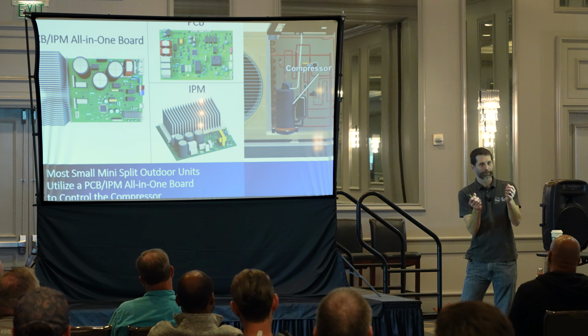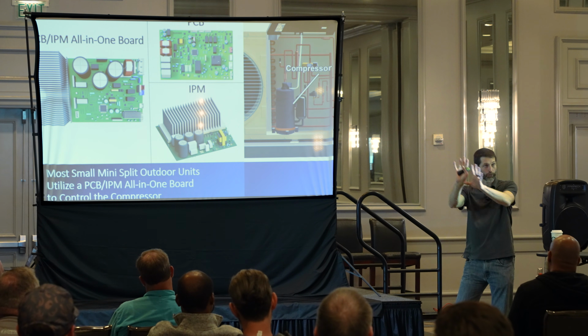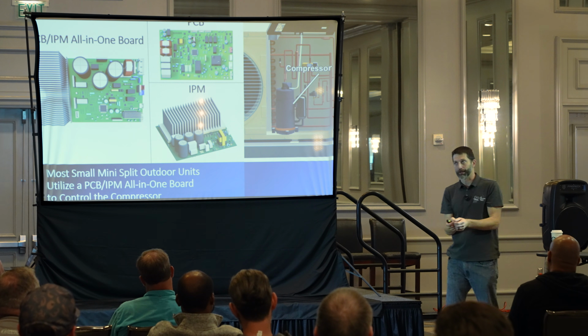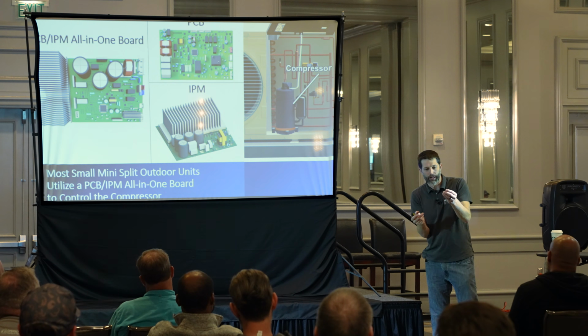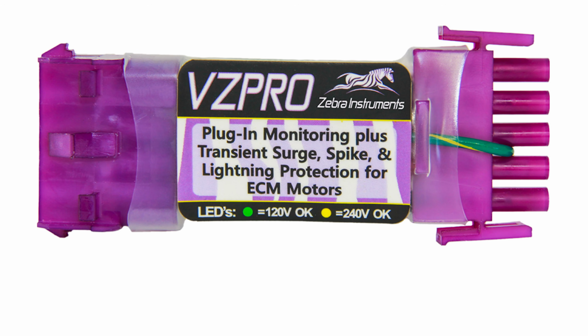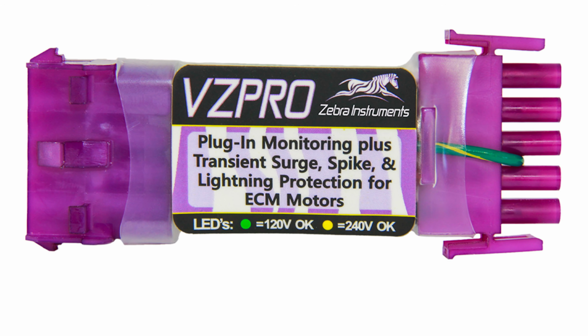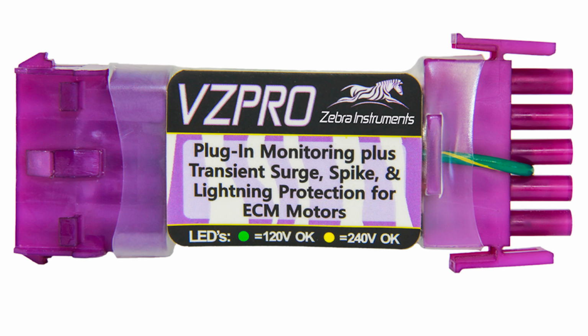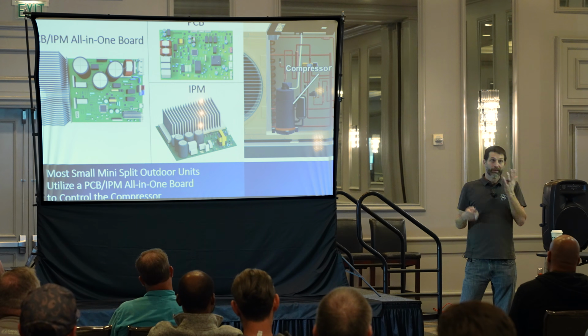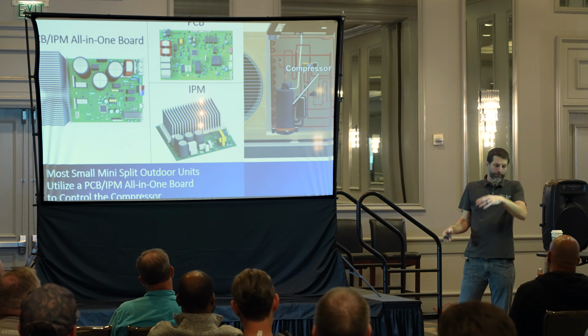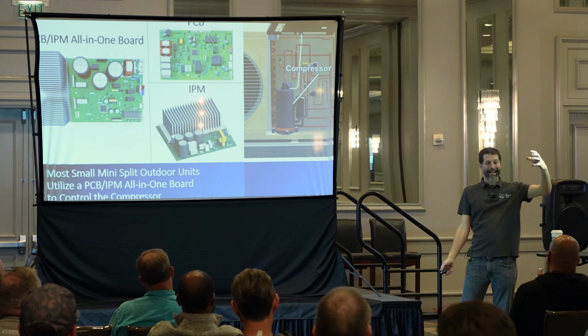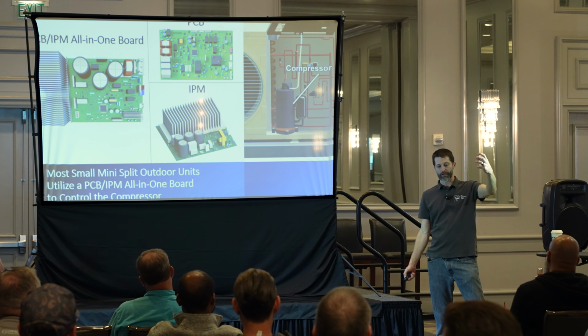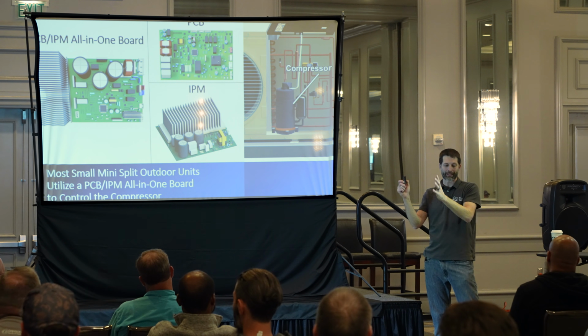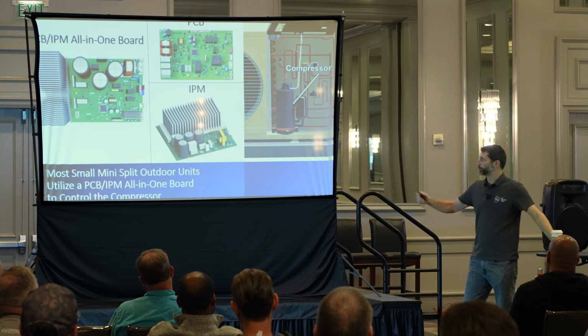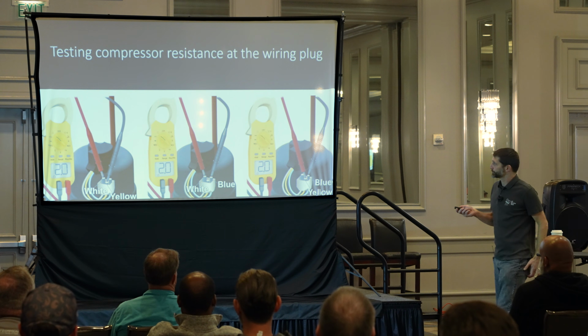There are third-party manufacturers, not equipment manufacturers, like Zebra and others, where you unplug the ECM motor, the ECM 3.0, and plug the surge protection in between the power harness and the board. But that's only protecting that part. So if you put surge protection at the inlet of the system on the power lines, then it's going to protect the whole system. Anyway, we'll get to that here.